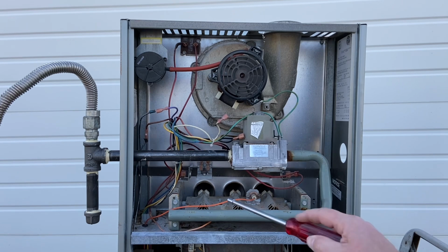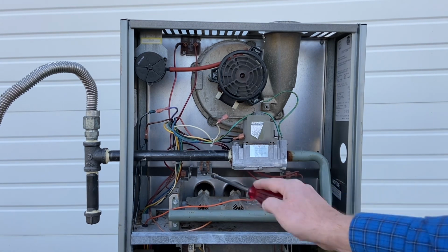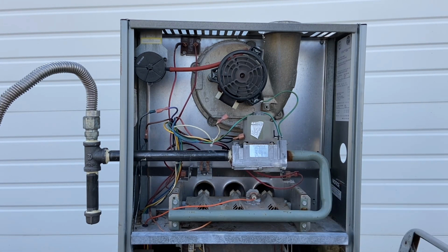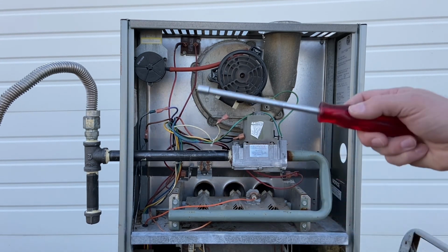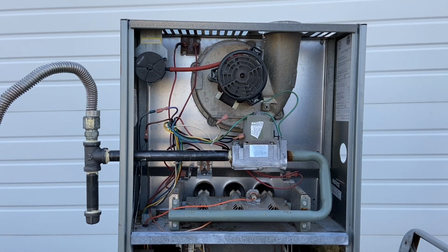Also, I want to show the importance of these limit switches. If they trip, that's significant. So if those limit switches trip, you need to find the cause of it. And again, this is why we like to stand to the side of the furnace when it ignites. Because if you were standing here in the front, something happened, it ignited, that flame comes out this direction, lose your eyebrows. So make sure everybody's safe. Don't do stuff like this. Don't bypass safeties. Make sure everything's working by the manufacturer's specification.